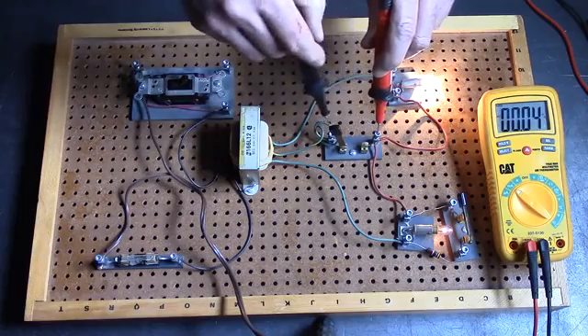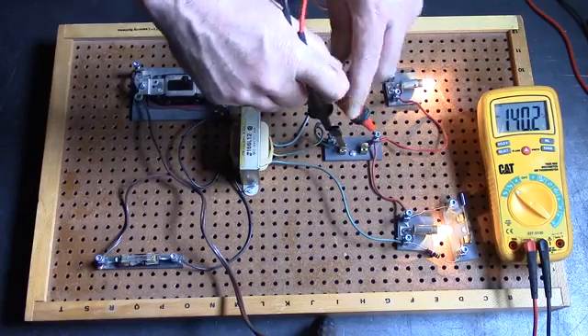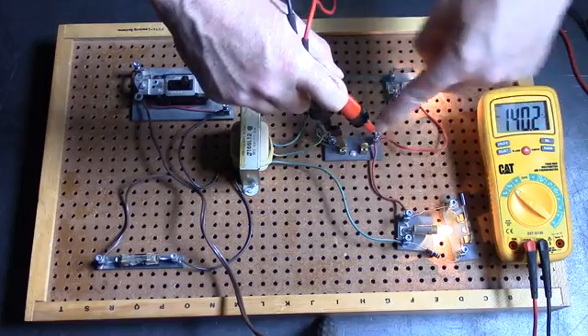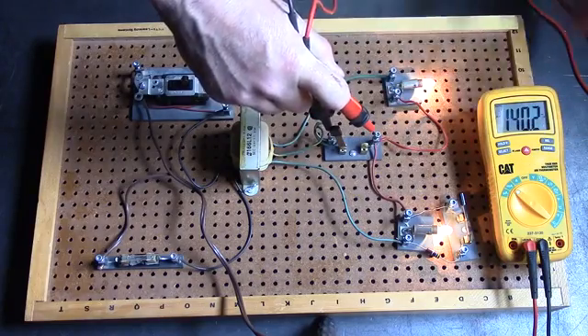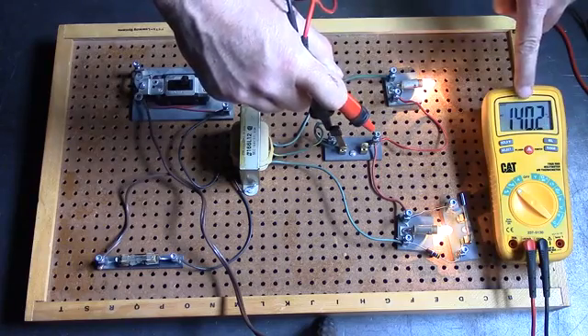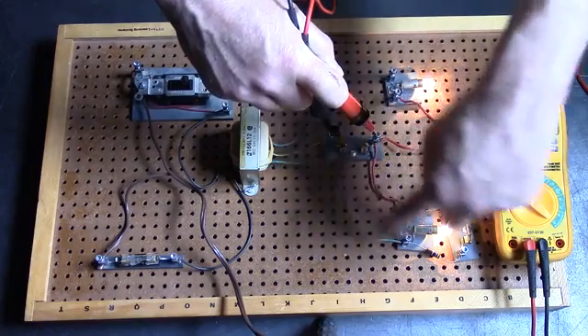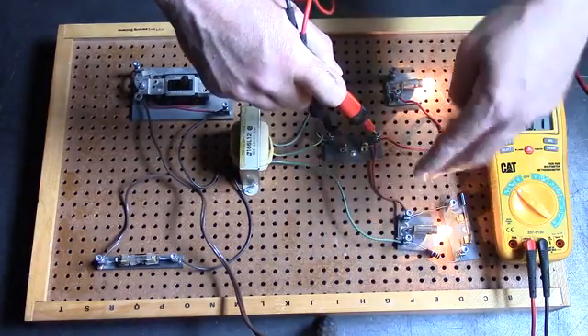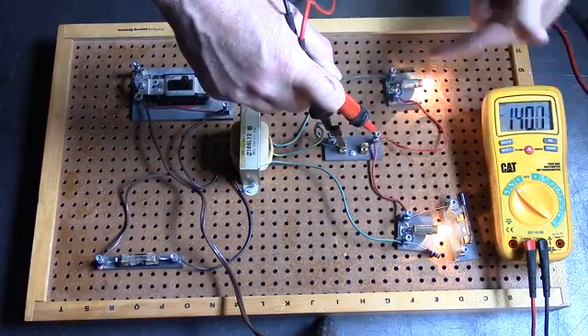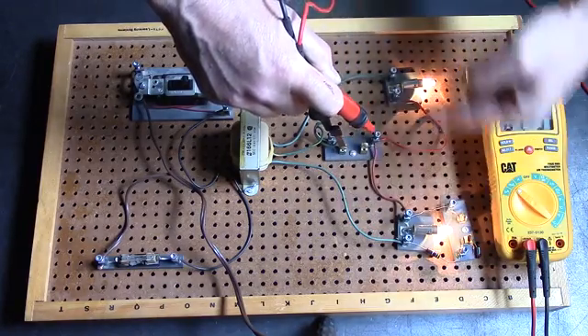What I'm going to do is just open the neutral switch but then I'm going to use my multimeter to close it again and I'll let the current flow instead of through that switch blade, I'll go through my multimeter to rebalance. And it's showing I've got about 140 milliamps flowing through the neutral path where my ammeter has been connected. So what that's representing is the imbalance between the two sides of the circuit. I've got 140 milliamps more flowing on this side because I've got more load and I can see that on the neutral. So when the neutral carries current is when we've got an imbalance in loads.